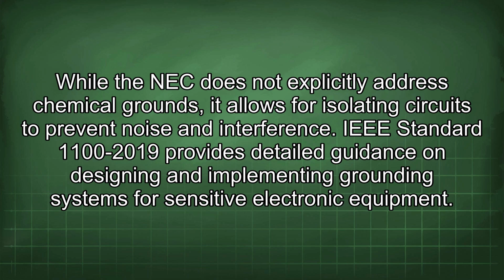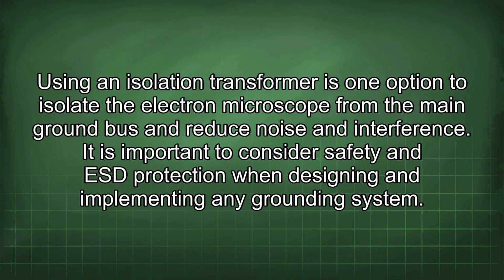IEEE Standard 1100-2019 provides detailed guidance on designing and implementing grounding systems for sensitive electronic equipment. Using an isolation transformer is one option to isolate the electron microscope from the main ground bus and reduce noise and interference. It is important to consider safety and ESD protection when designing and implementing any grounding system.